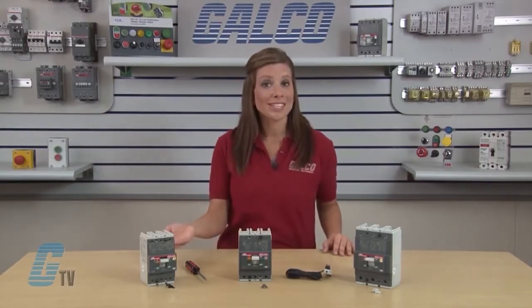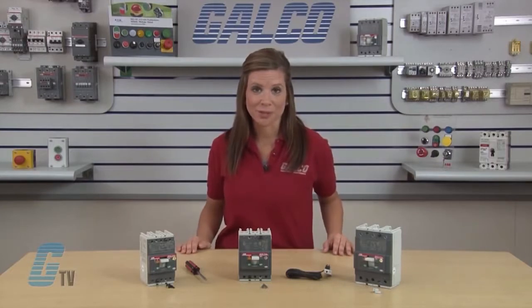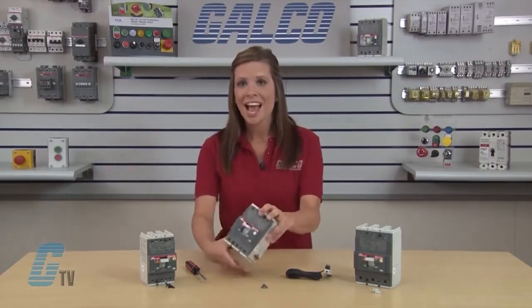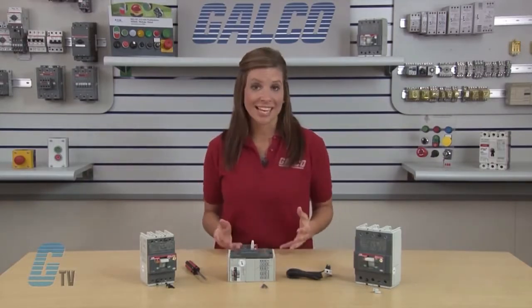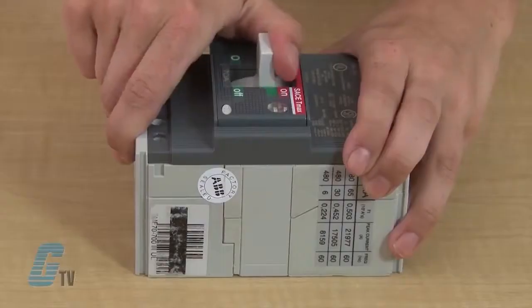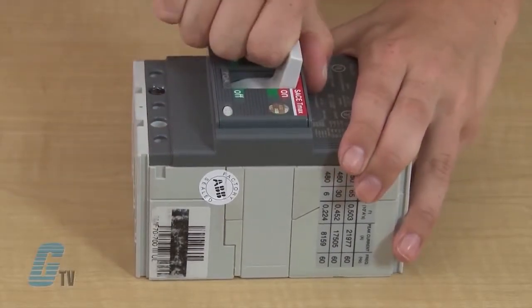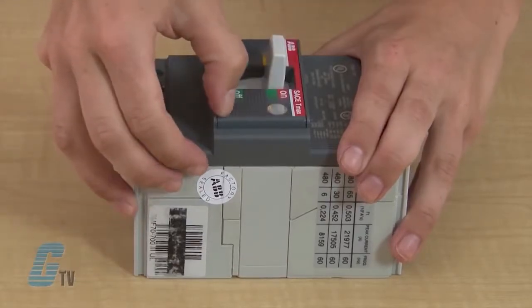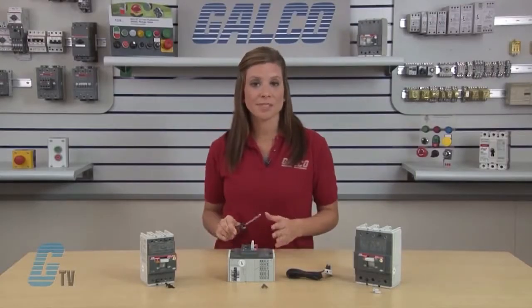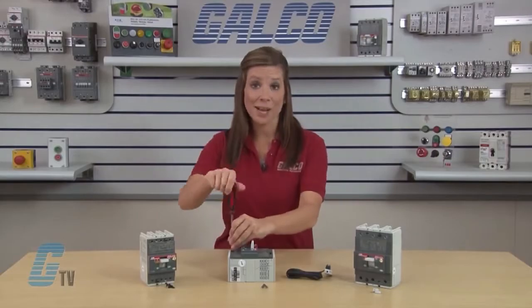These are the T1, T2, and T3 circuit breakers. To install the auxiliary contact, I will need to set the circuit breakers in test position by switching the breaker to off, then on, and then by pushing the test button here. Once they are in test position, I can remove the screws and take off the front plate.